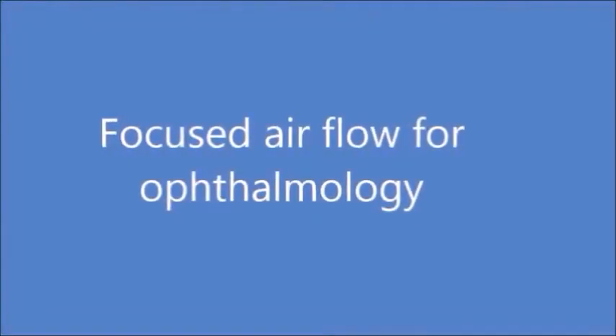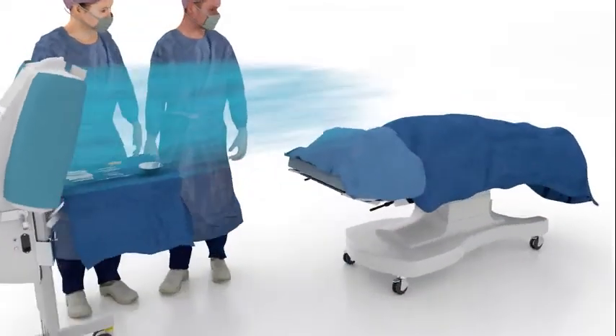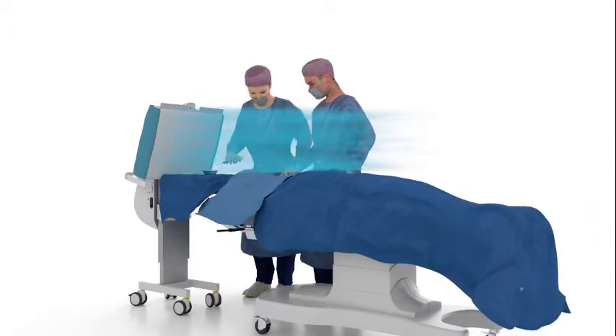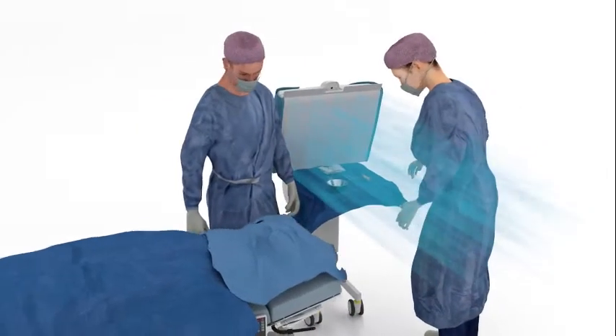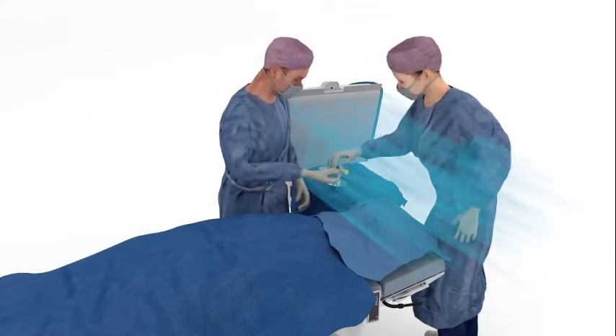Focused laminar flow for ophthalmology. Operio is a focused laminar flow unit positioned in the perioperative area directly on the surgical wound, without introducing obstacles into the zone.